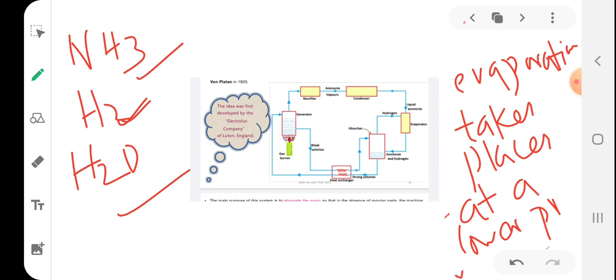The mixture of ammonia vapor and hydrogen is passed through the absorber, where ammonia is absorbed in water while the hydrogen rises to the top and flows back to the evaporator. So this completes the cycle. Okay. So this is the working of the Electrolux system. The Electrolux system consists of three fluids: hydrogen, ammonia, and water. Hydrogen is a gas which is used to enhance the process of evaporation, ammonia is the refrigerant, and water is the absorbent.